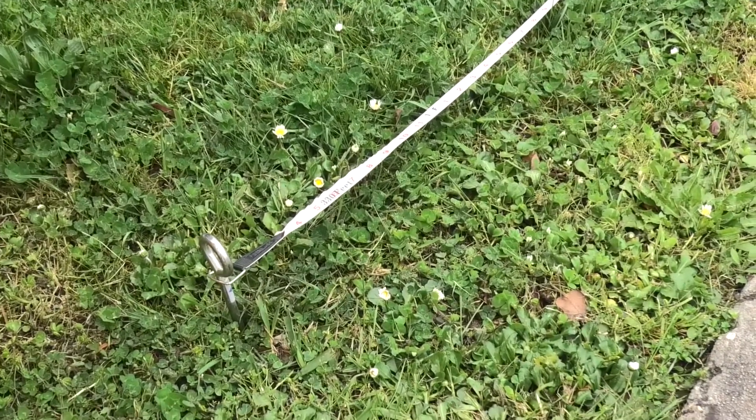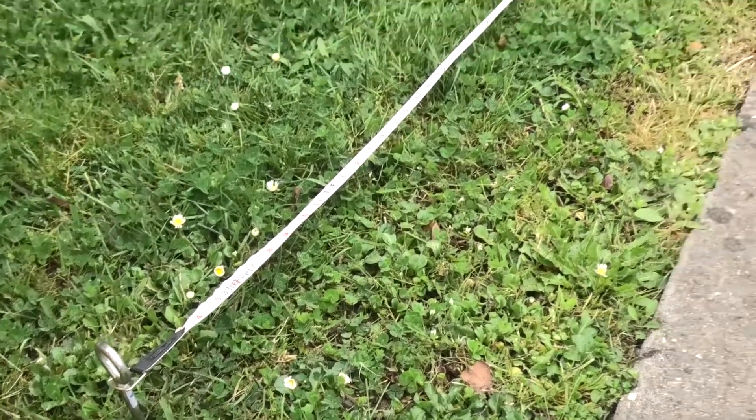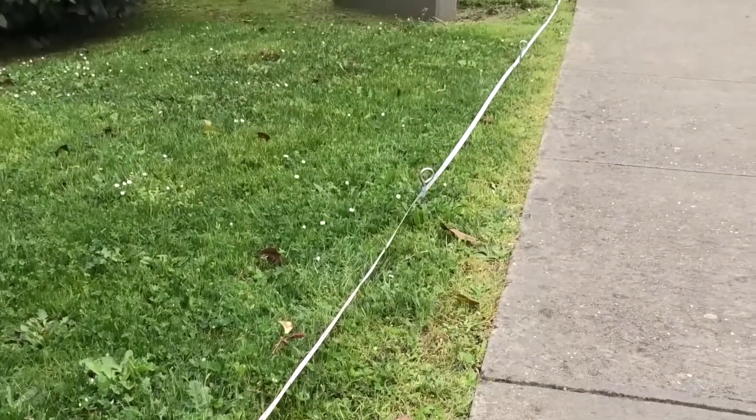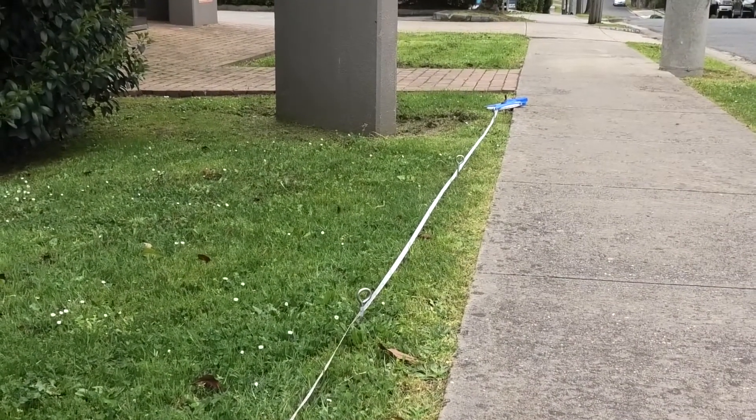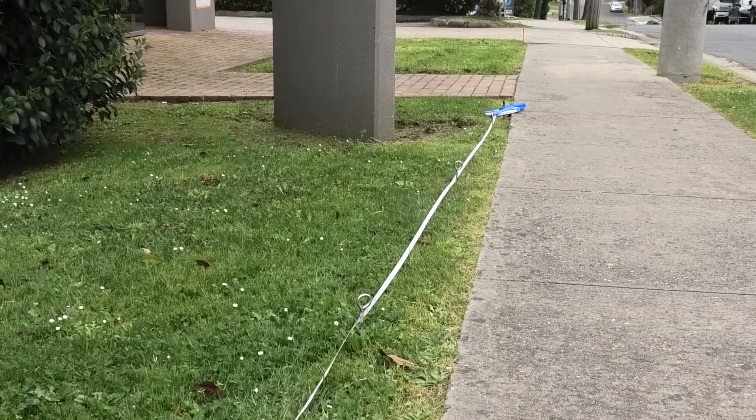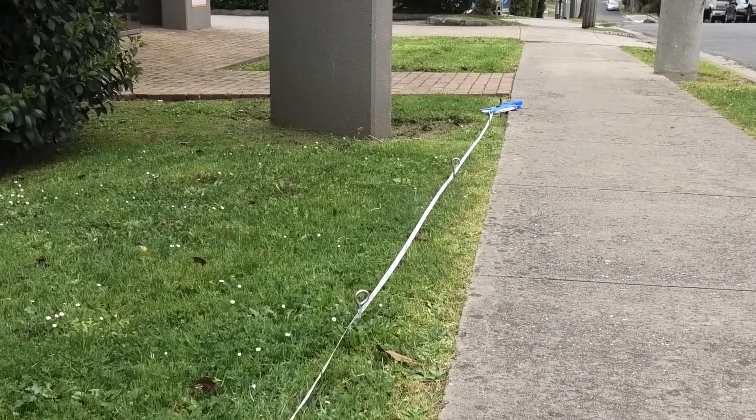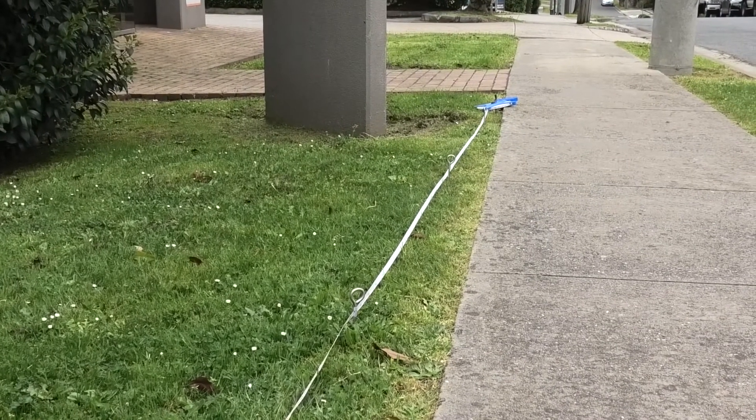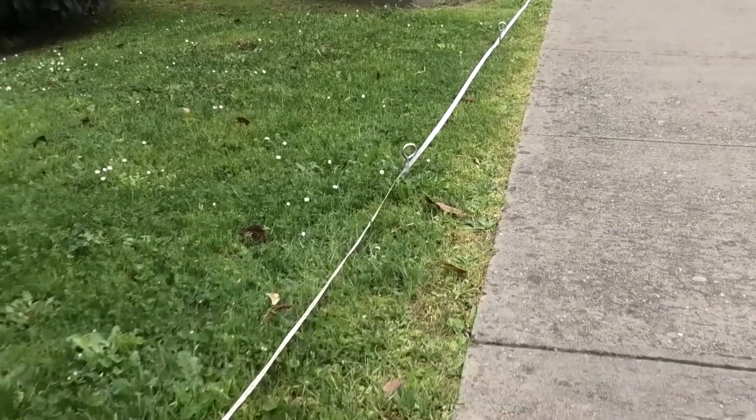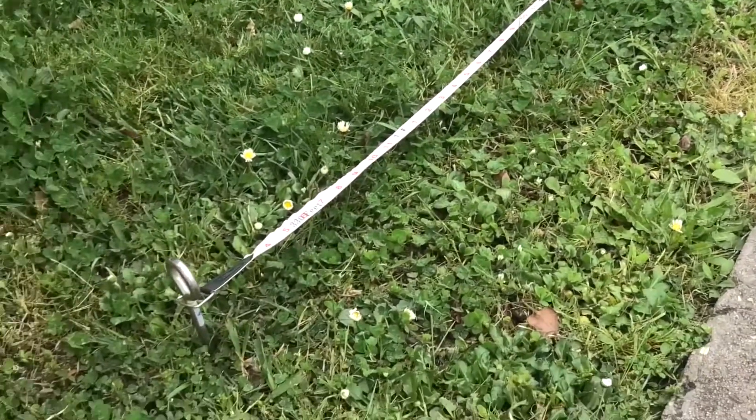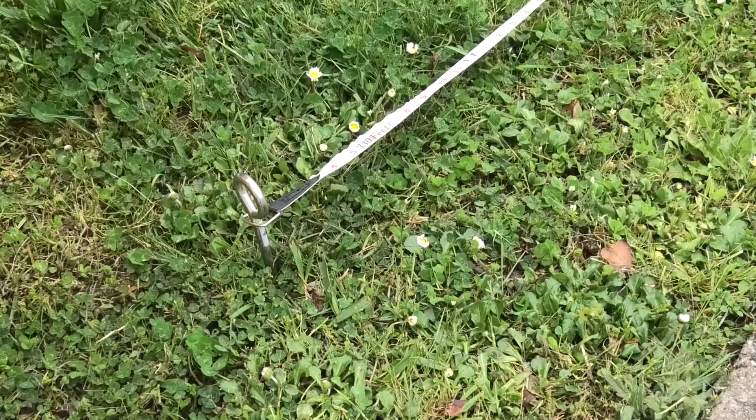I've found the spikes, the stakes in the kit and I've inserted them. I'm only doing two metres spacing. In this instance, it means the fact that I have to keep the spacing, the depth has to be less than 1/20th of the spacing, so these spikes should not be inserted more than 10 centimetres in the ground.